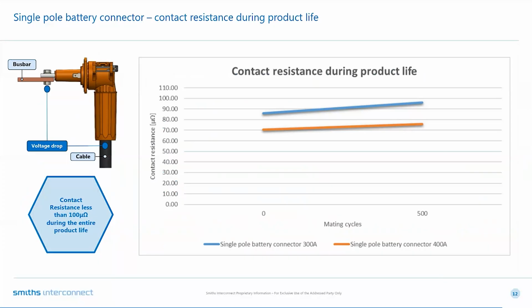We will now present the main electrical results obtained during product validation. The first test performed is contact resistance during product life. In the top left image is shown the configuration tested, where we have the receptacle screwed on a copper bus bar and the plug crimped on two different cable sizes. The 50 square millimeter for the 300 amps version and the 95 square millimeter for the 400 amps one.